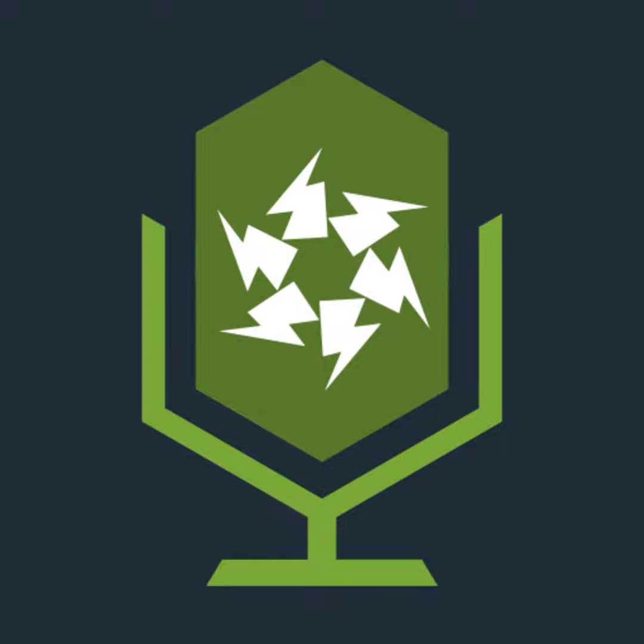We're keeping it simple, so we're not going to do 3-phase or anything right now. I can do some more examples on this kind of thing if we decide that we need it. So power over voltage, 10,000 over 230, 43.478, so 44 amp. IB is equal to 44 amp. Power over voltage, P over V.